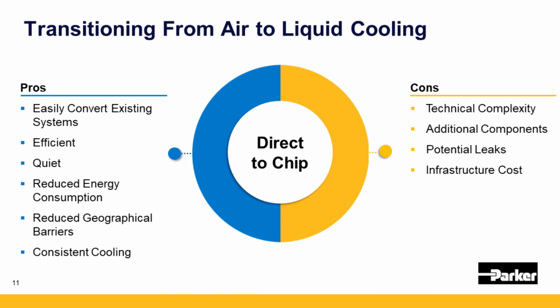In terms of transitioning from air to liquid cooling with the direct-to-chip style, typically you can add this into an existing data center. There are a number of ways to add liquid cooling - maybe a rear door heat exchanger, or sidecars, different ways to reject heat that you can retrofit into an existing system today. They can be efficient and quiet, and they reduce the energy consumption necessary.